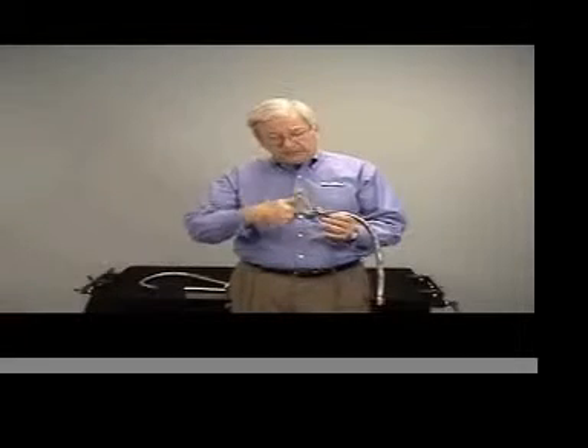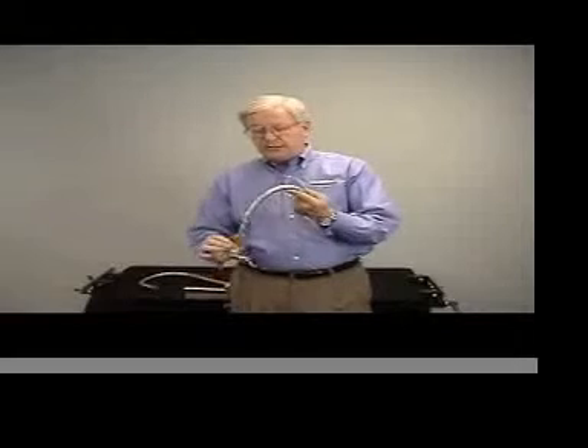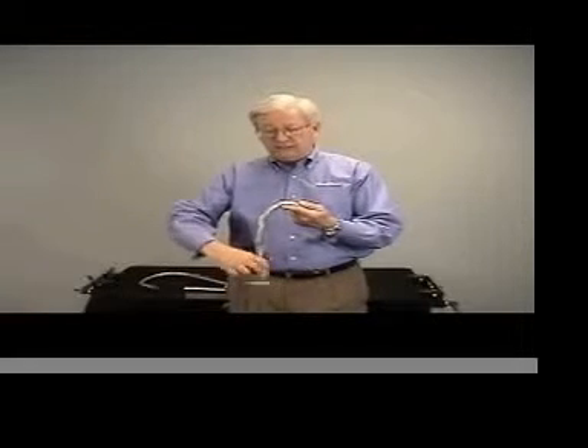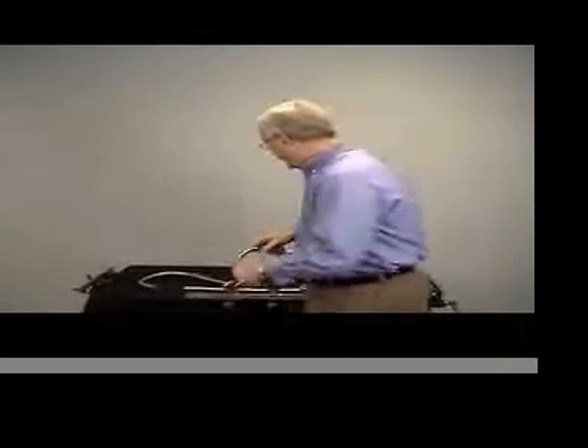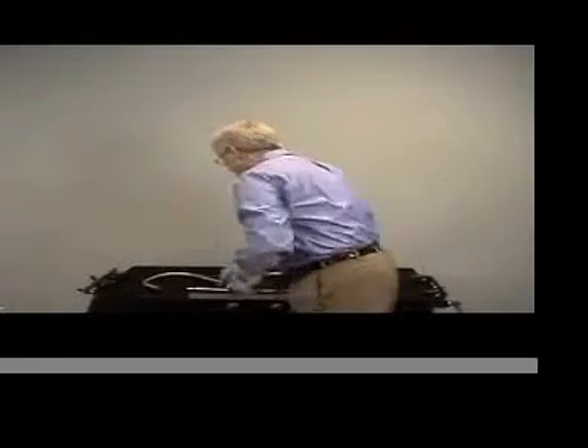Now, before you send an arm for cleaning and sterilization, we need to open it back up again. And the method to do that is exactly the opposite. Again, make sure that it has been loosened at the tensioning knob all the way, turning it counterclockwise, and then holding the arm in your left hand, twist the entire housing in a counterclockwise manner until you see space begin to appear and the cable is visible. Each of the devices is done the same way.